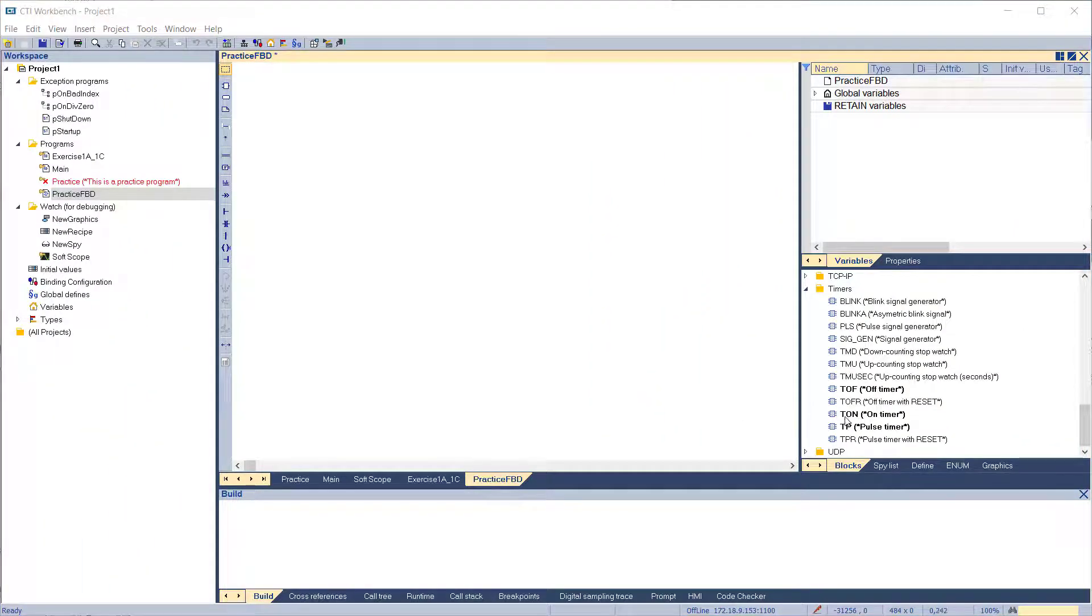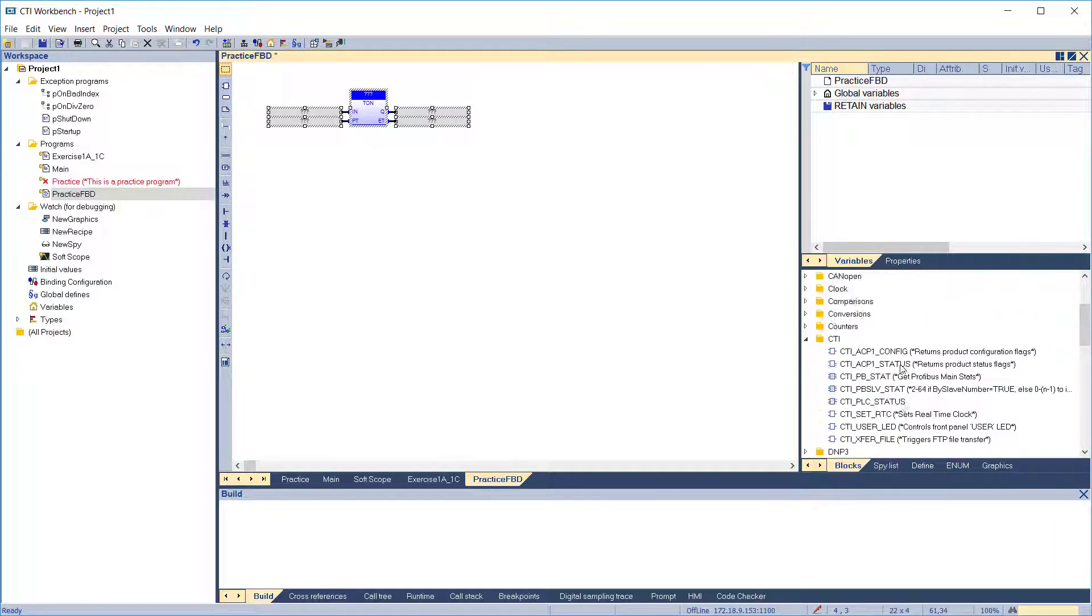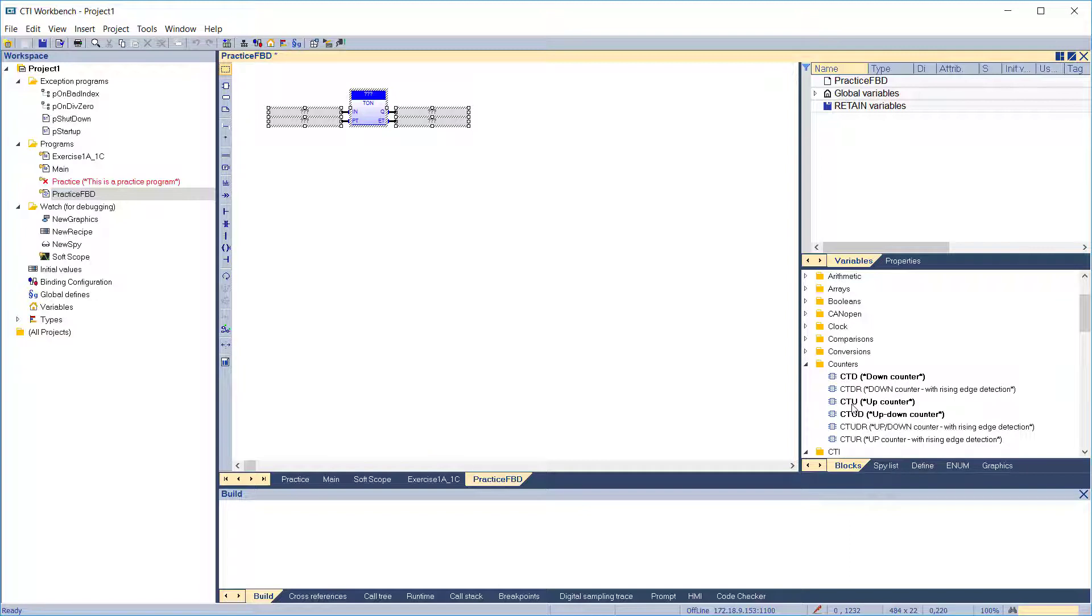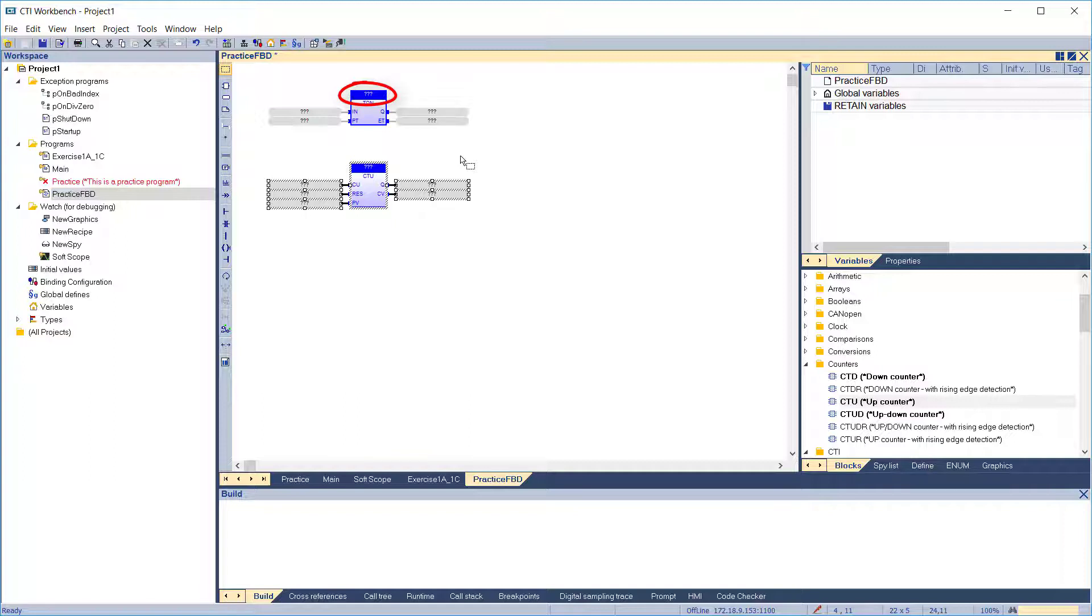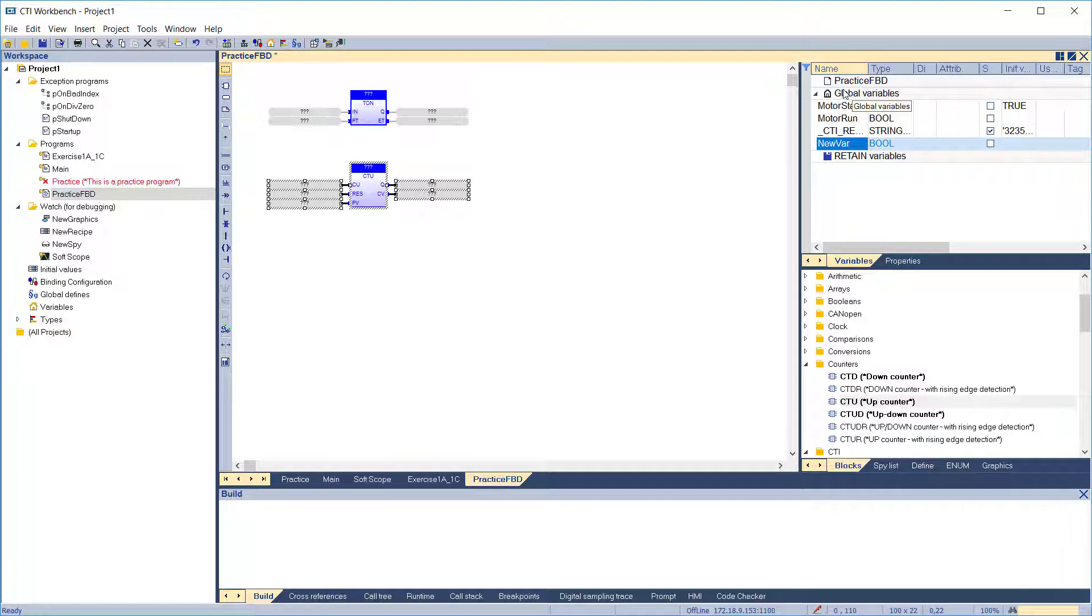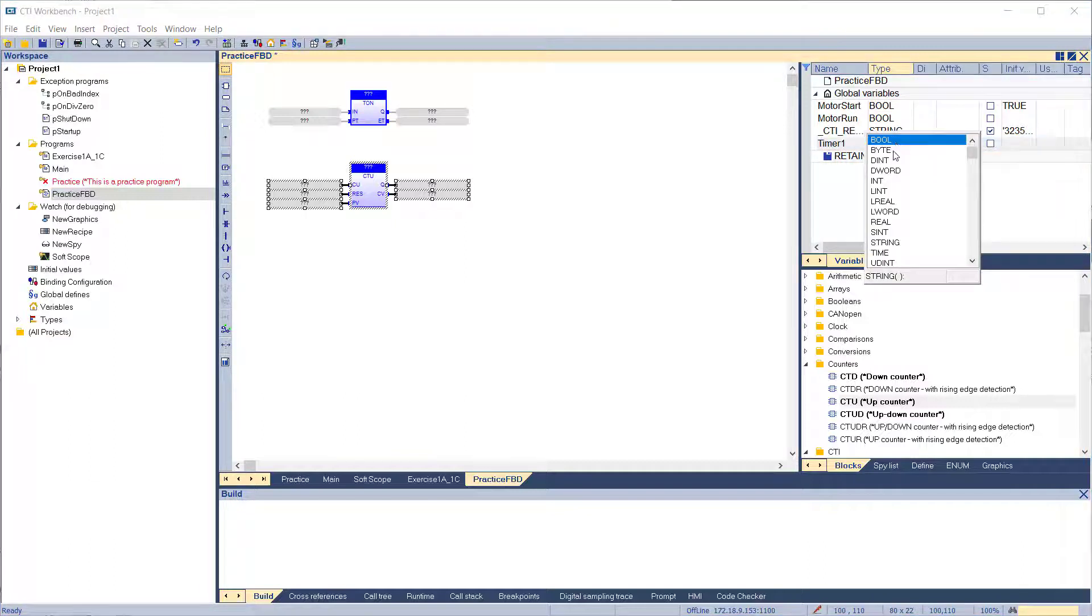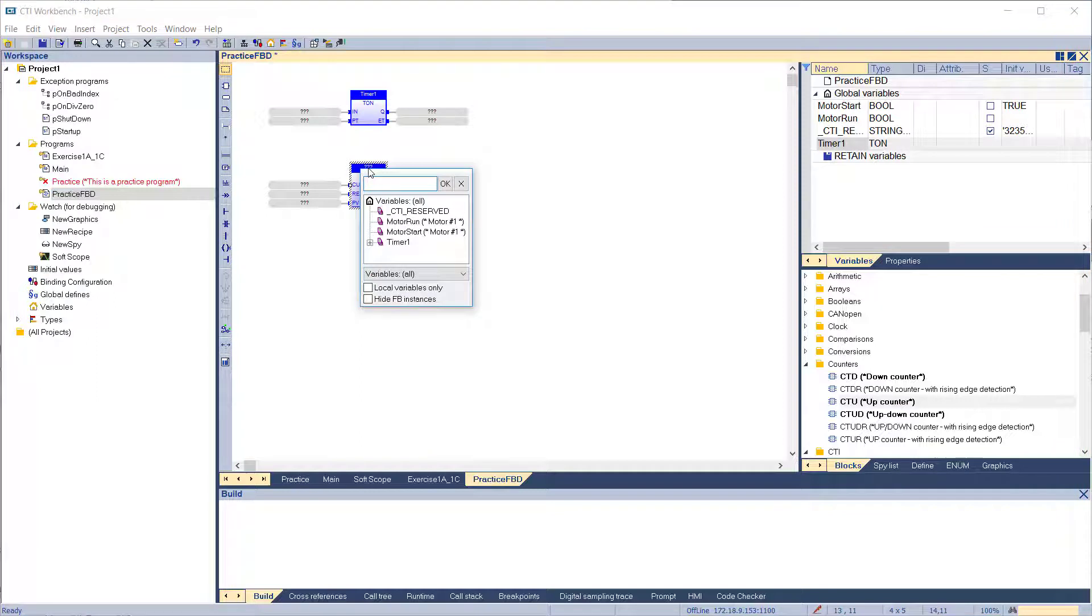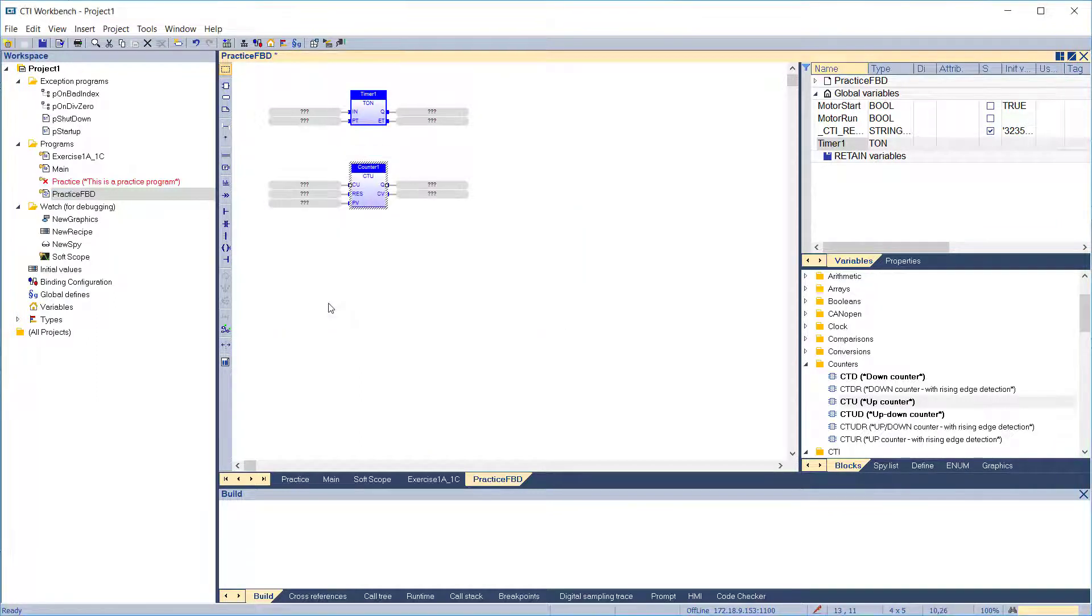To use a function or function block in your diagram, simply drag it from the list to the desired location. For function blocks, you will notice they come in with question marks at the top. This is the space for the unique variable name of this instance and needs to be filled in. If you have already defined a variable name for this instance, just drag it from the variable list into the function block. You can also define a new instance by double-clicking on the function block and completing the variable definition dialog.